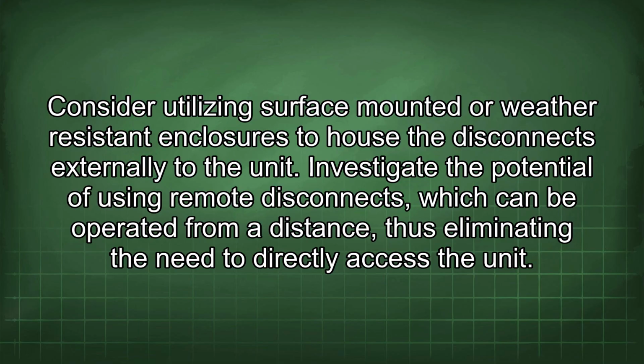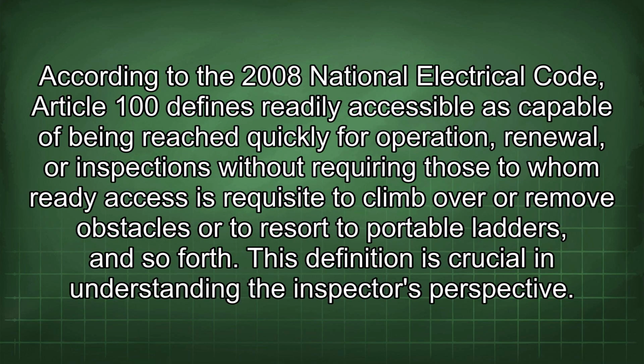access the unit. According to the 2008 National Electrical Code, Article 100 defines readily accessible as capable of being reached quickly for operation, renewal, or inspections without requiring those to whom ready access is requisite to climb over or remove obstacles or to resort to portable ladders, and so forth. This definition is crucial in understanding the inspector's perspective.